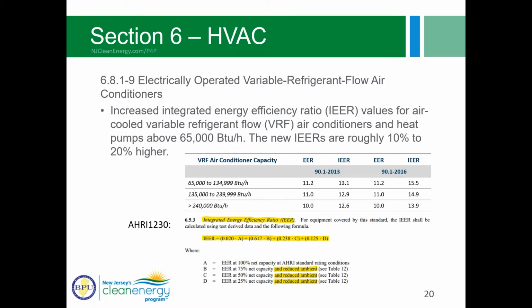And Table 9 for electrically operated variable refrigerant flow air conditioners. This is a popular system, and we do see lots of these. There are many of these that exceed these published minimum efficiency values. As you can see here, the 2013 values are listed in the center column, and the 2016 values are on the right. You'll notice that the EER is the same, but the IEER is increased slightly. That's the integrated energy efficiency ratio.